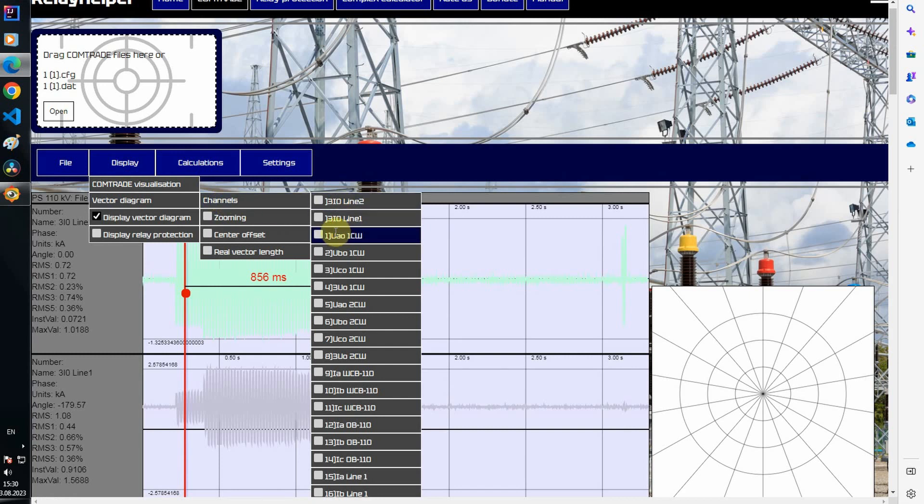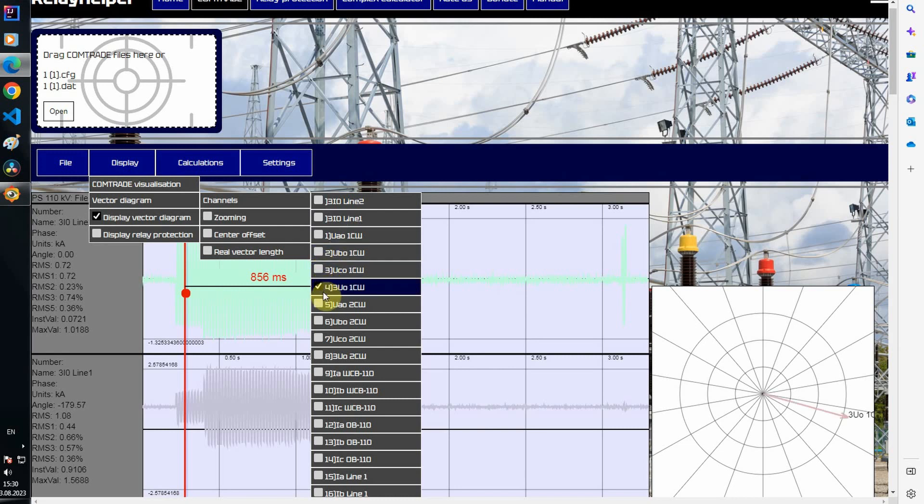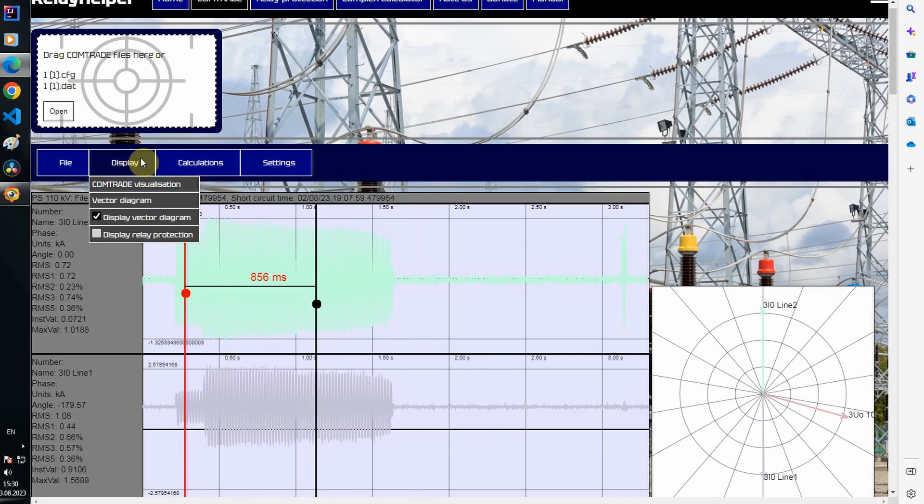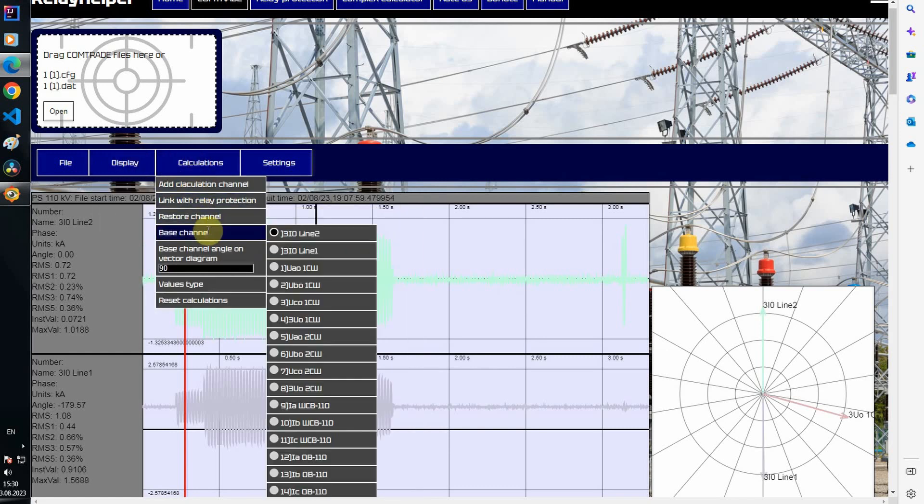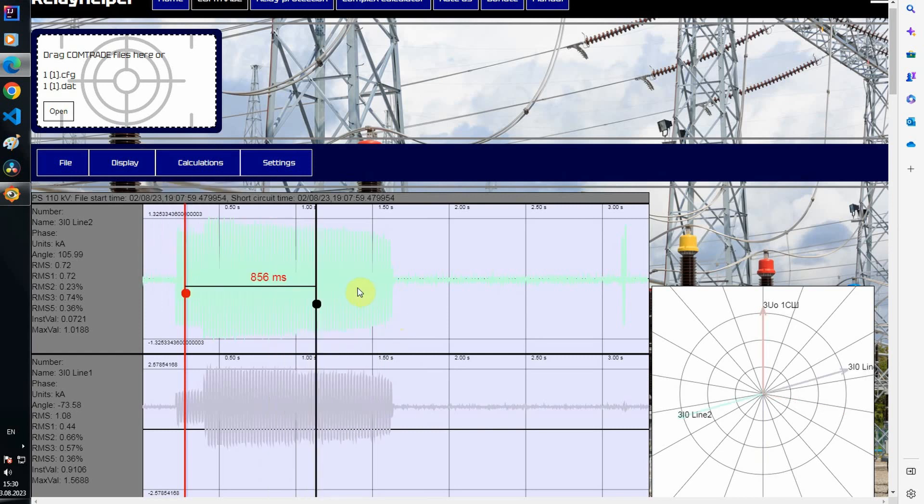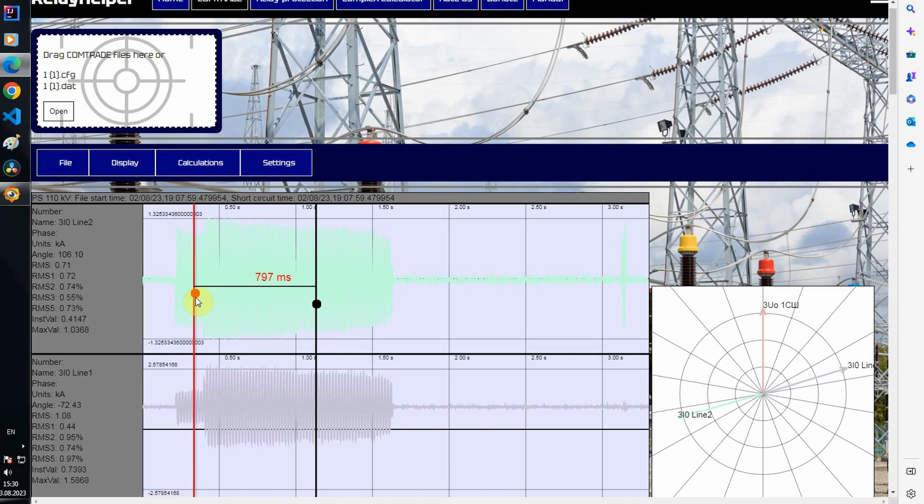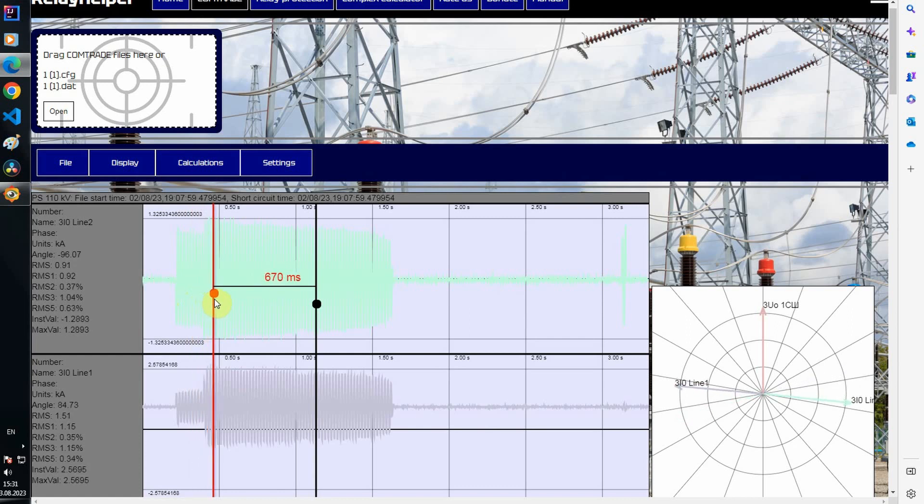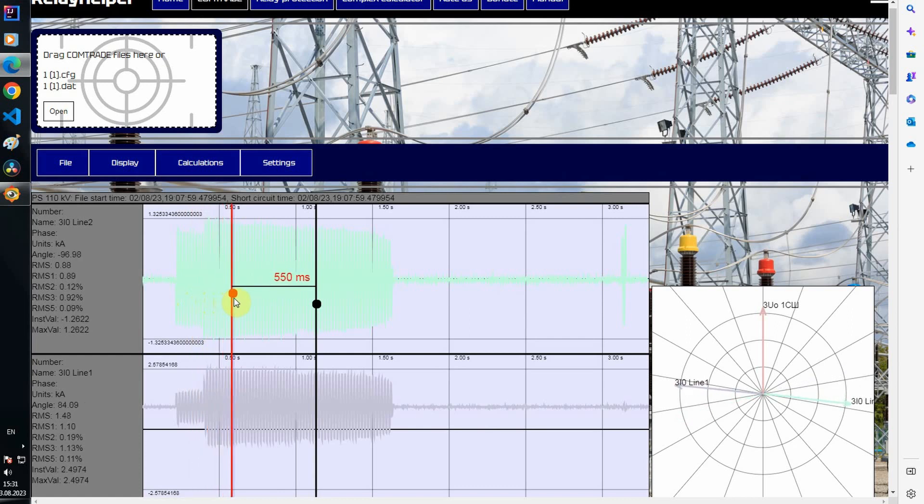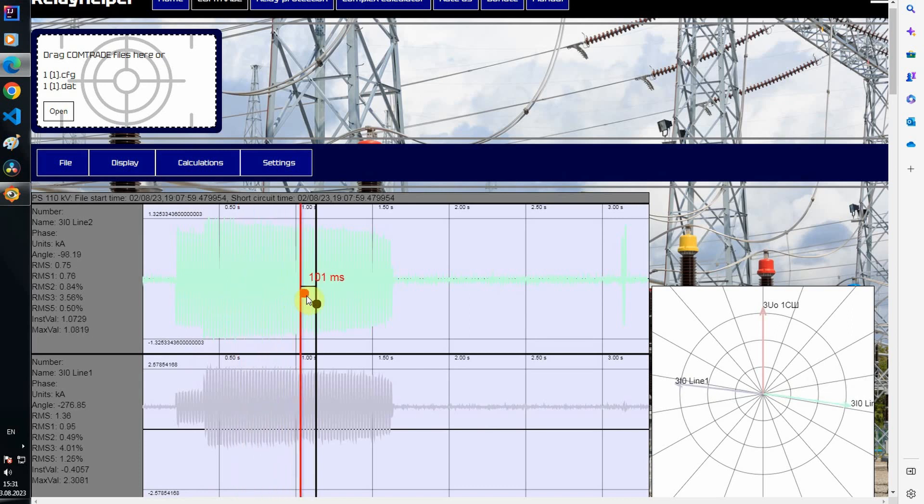I add the zero sequence voltage measured by the voltage transformer and the calculated channels. I choose the zero sequence voltage as the base channel. It can be seen that the zero sequence power was first directed to the second line at all, and only after disconnection from the power end the zero sequence power began to be directed to the first line.